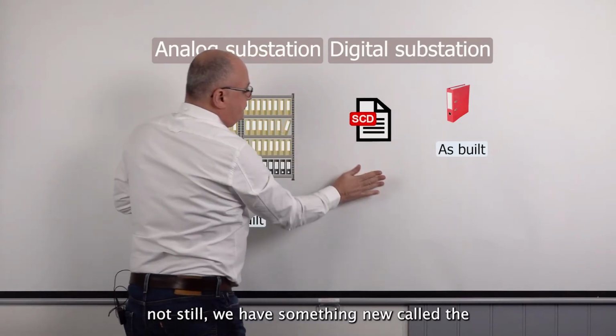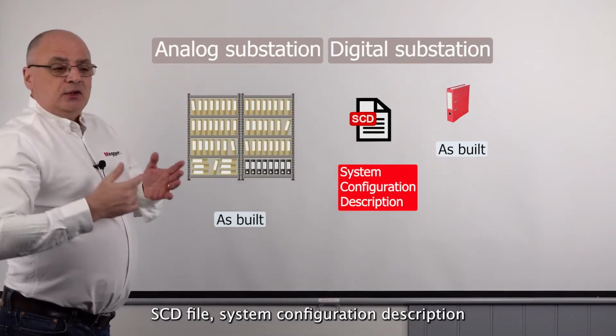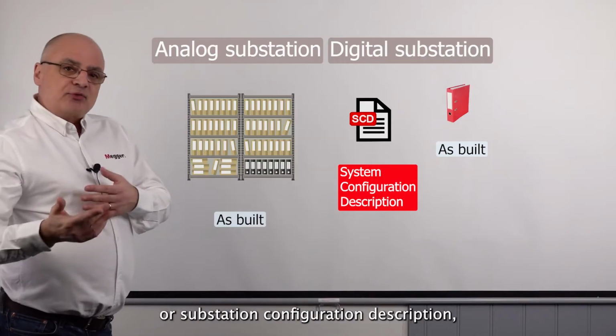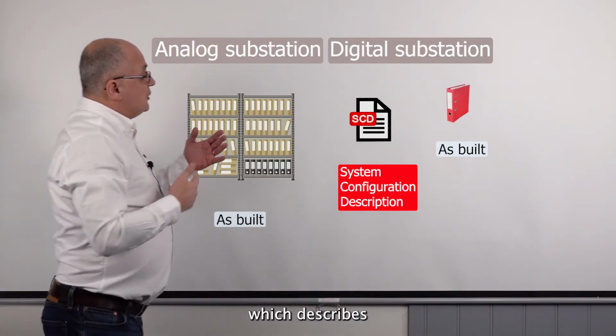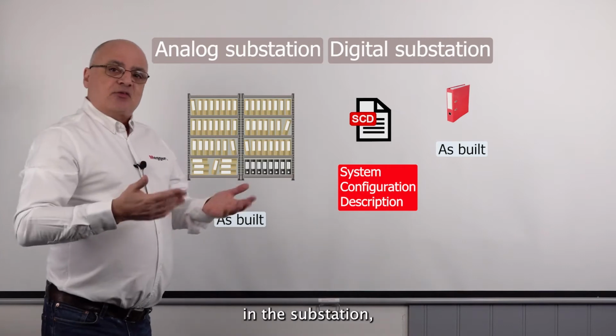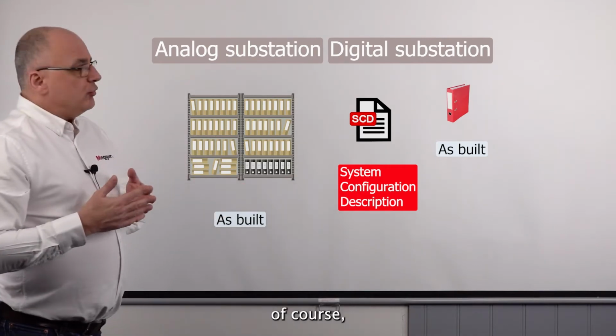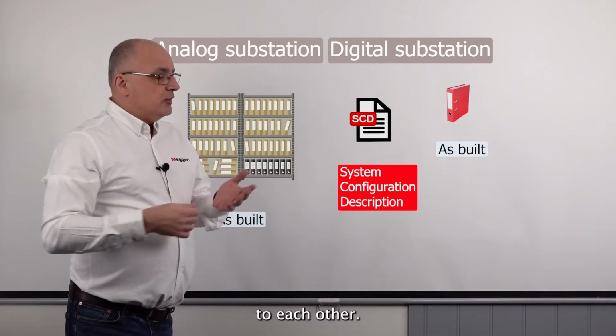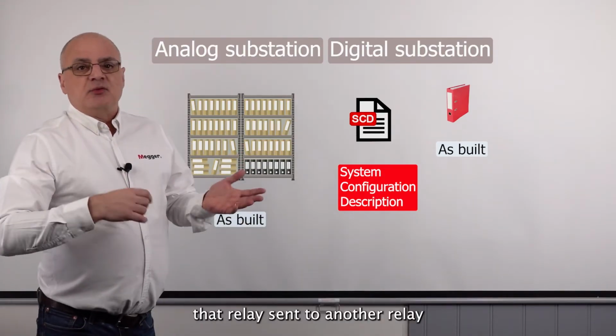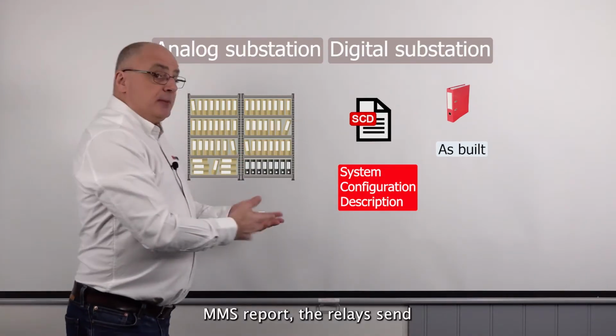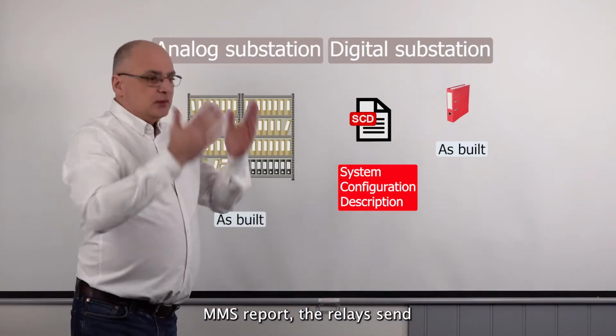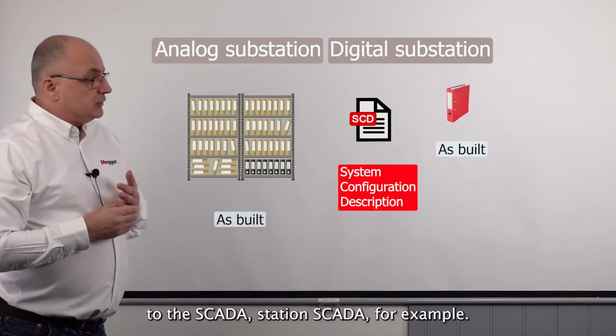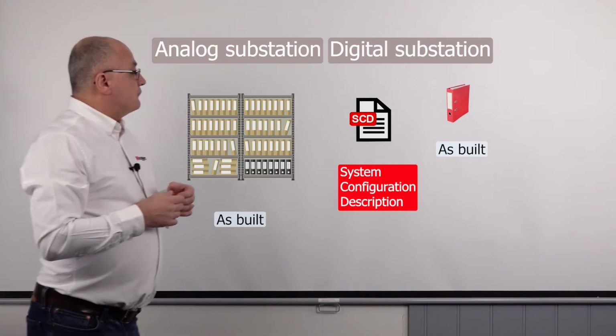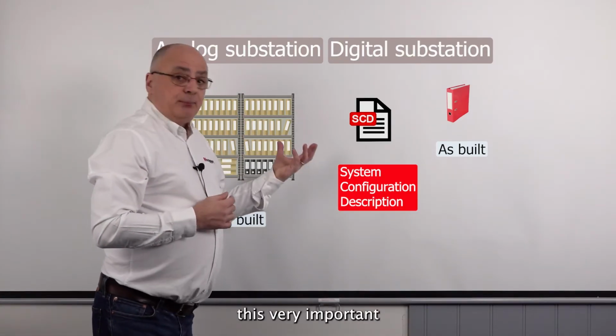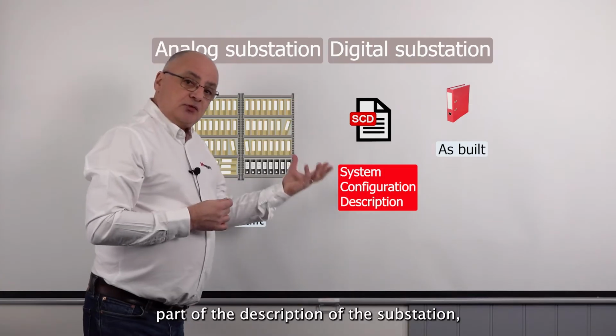But we also have something new: the SCD file, System or Substation Configuration Description, which describes all the devices in the substation—numerical devices, and everything they send to each other, like GOOSE messages between relays, or MMS reports relays send to the station SCADA. This is a very important part of the substation description.